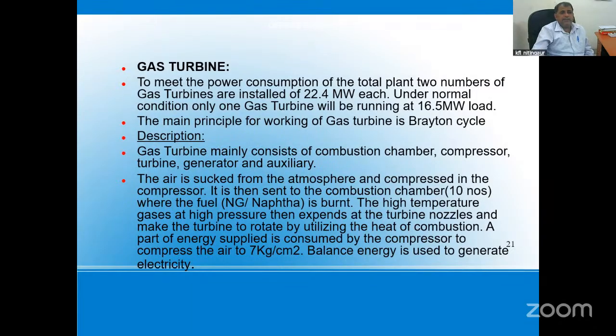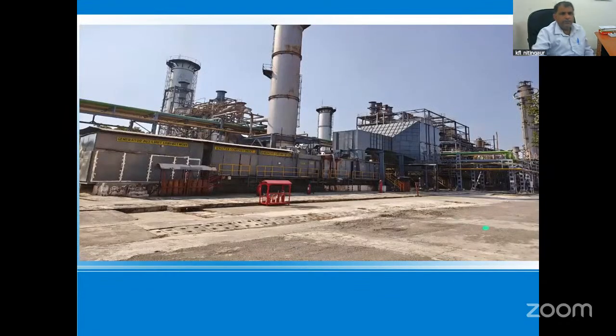The high temperature gases at high pressure then expand at the turbine nozzle and make the turbine rotate by utilizing the heat of combustion. As and when it reaches sustainable speed, our driving system declutches from the turbine shaft, and now the turbine rotates with the help of combustion gas. This is the gas turbine plant.